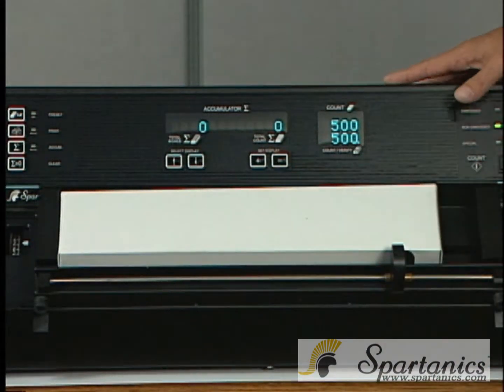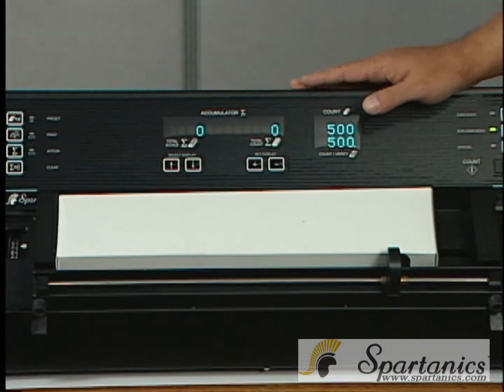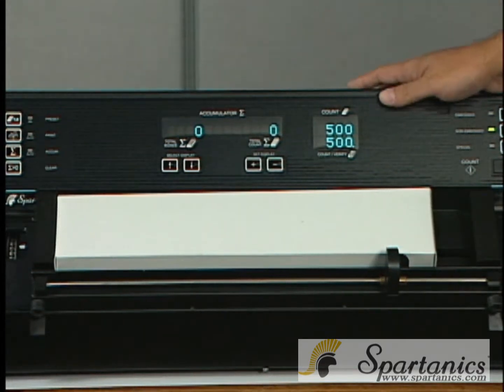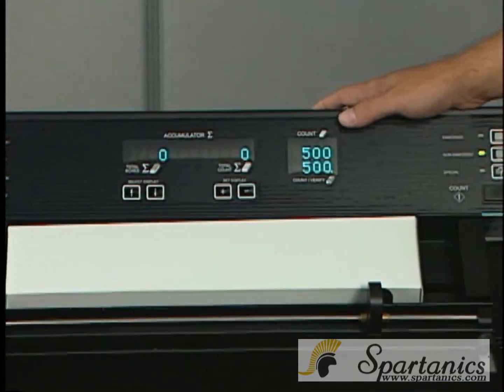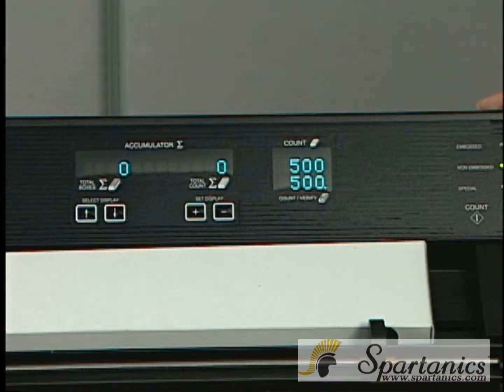At this point, I'd like to say that when this machine starts counting the first pass, it is counting with 2 channels, and 2 channels on the way back. It'll be a total of about 3.5 seconds to count and 3.5 seconds to verify it. So it's a total of 7 seconds.